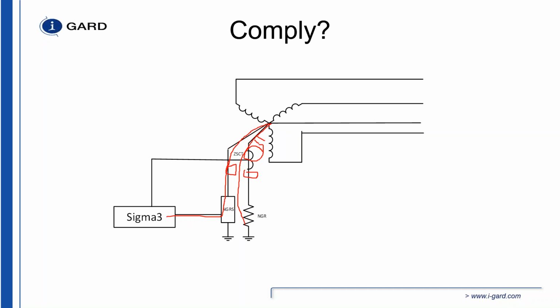And this comes from M421, and we've been using this for a long time. However, we used to do it a different way. We had a DC voltage impressed upon the NGRS here, and we would measure the continuity of that path. Unfortunately, because we have a DC voltage impressed upon here, we couldn't tell if there were other issues. So if you had a short here, it would not monitor that. But M421 only required us to monitor whether that resistor was in an open state, not necessarily in a shorted state.